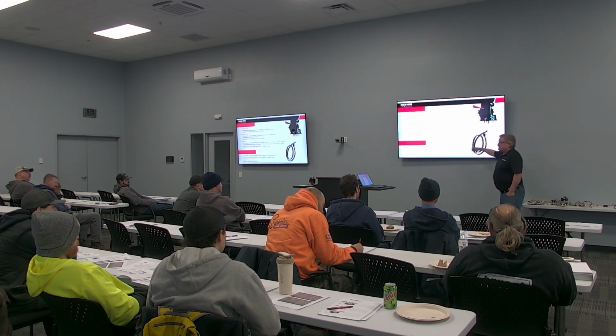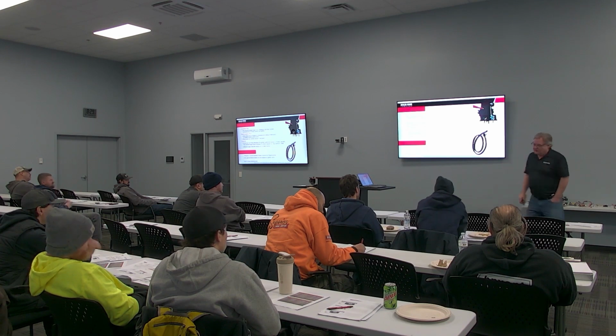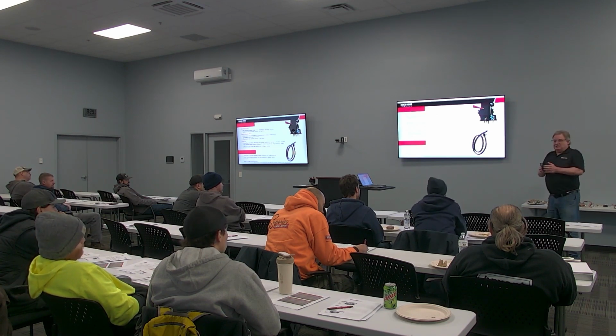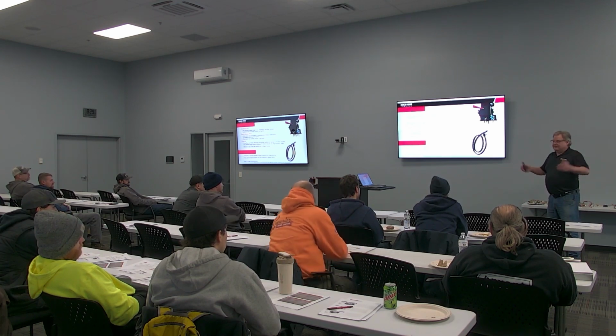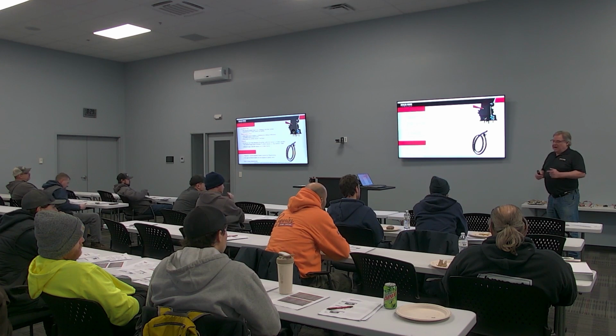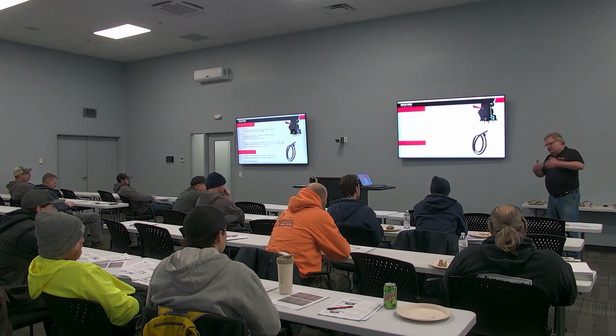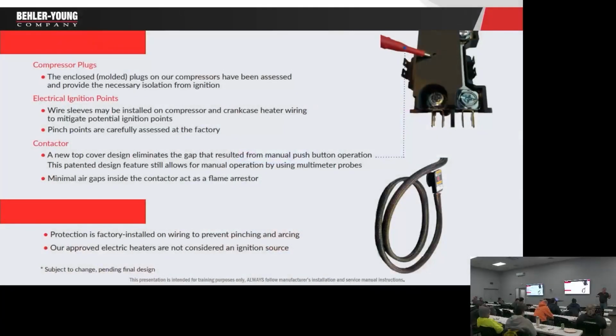Some of the other things you're going to see are the braided covers on the compressor wiring and some of the other wiring, to prevent pinching. Well, if it's hard to ignite, why are they doing all this? Well, they're covering their butts, is what they're doing. However, again, I don't want to underplay the A2L, but at the same time, I don't want to be afraid of it. But when they put stuff like this on there and we take it upon ourselves to remove it because we didn't have that contactor, and there's a fire in that building, regardless of whether that caused it or not, they're going to find it. So my suggestion is put that contactor back in. Don't eliminate this board.